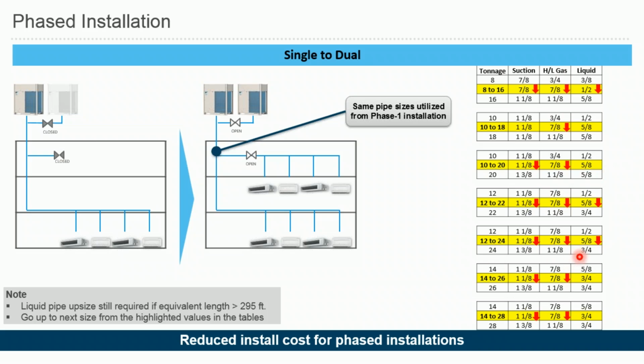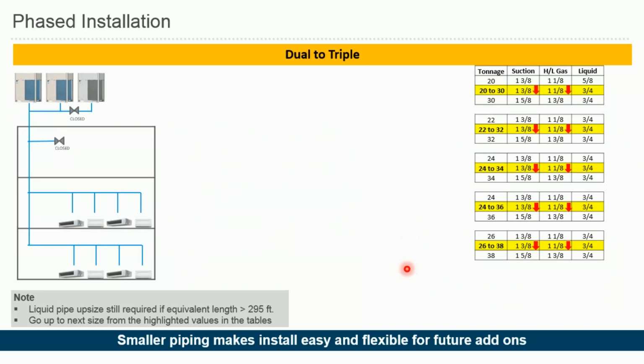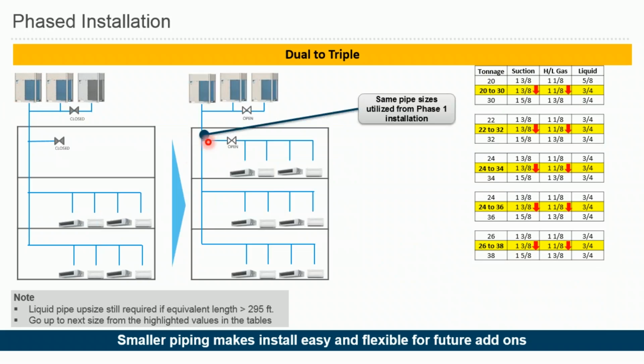So that's the idea, and that gives you more flexibility when it comes to design, and allows you to reduce the initial upfront costs at the beginning of the project. It's a similar idea when switching from dual module configuration to triple module; you're following very similar rules with different pipe sizes that will be provided in our manuals as well. You'll be able to do that. And this will give you smaller pipe sizes, which leads to a reduction in your pipe installation and labor costs as well, which we'll see in the next few slides.